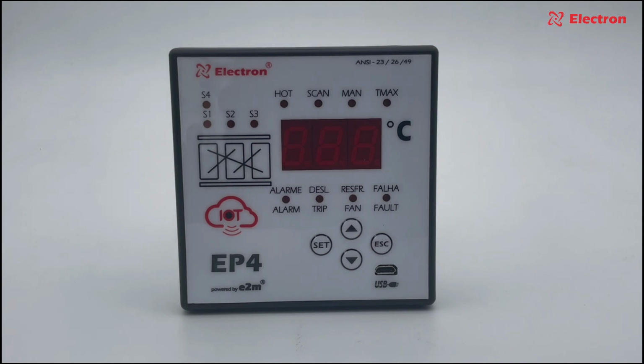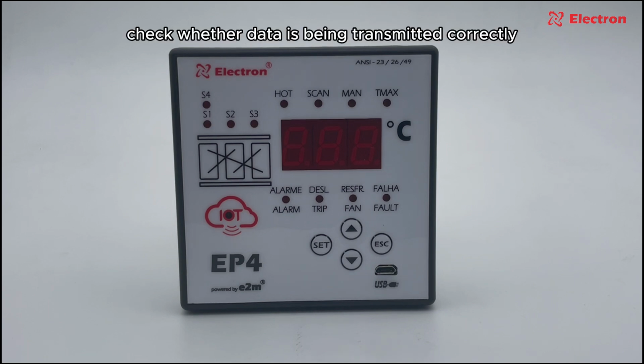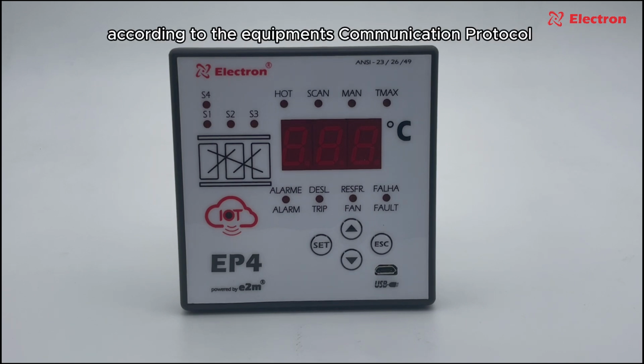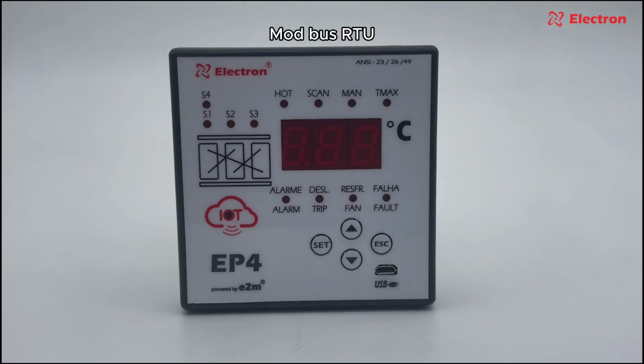3. Monitor data. Observe the data being transmitted on the RS-485 line using the monitoring device. Check whether data is being transmitted correctly according to the equipment's communication protocol, for example Modbus RTU.